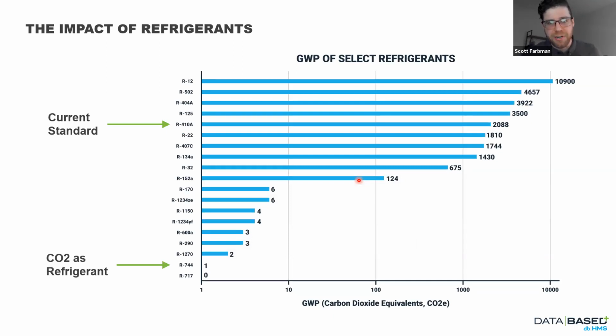So I just talked about refrigerant, and this is why refrigerant is so important to take a look at. Our current R410A that we use on most systems in our buildings has a global warming potential of just over 2,000. So it's 2,000 times more impactful than just CO2 by itself. And that could add up to be a lot. It depends what your system is. It depends how much refrigerant charge you have, and it depends how often that refrigerant leaks and you have to recharge it. And you'll see in a little bit how much that could add to the total carbon emissions of a building.